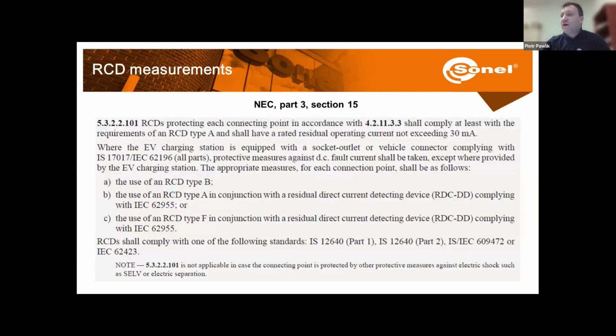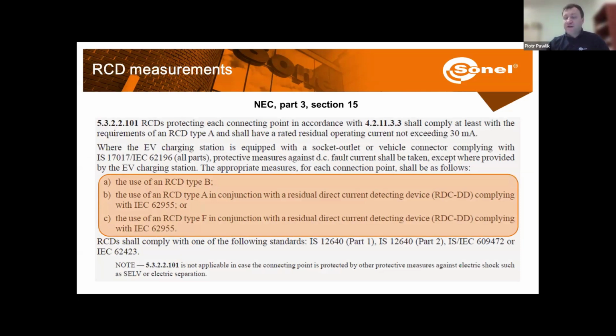And furthermore, in the National Electrical Code, we can find this information that the charging stations should be secured either with RCDs type B or with RCD type A with additional protection against DC leakage currents above 6 milliamps, or with RCD type F, again with the protection as per IEC 62955.